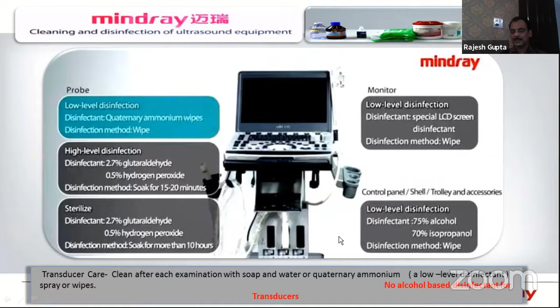The probes are not recommended to be disinfected with any alcohol-based spray. This needs to be taken very seriously. No transducer should be wiped with any alcohol-based spray or disinfectant solution. So this is the protection of the ultrasound machine and the probe. That's all about the do's and don'ts of maintenance of the equipment and the protection of the biomedical engineers and the paramedical staff. So thank you.